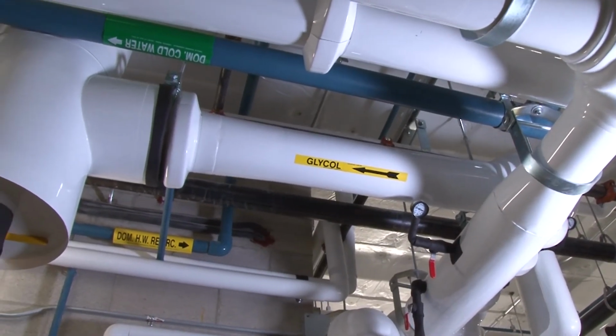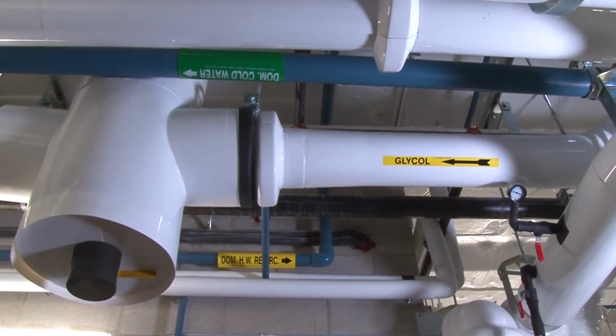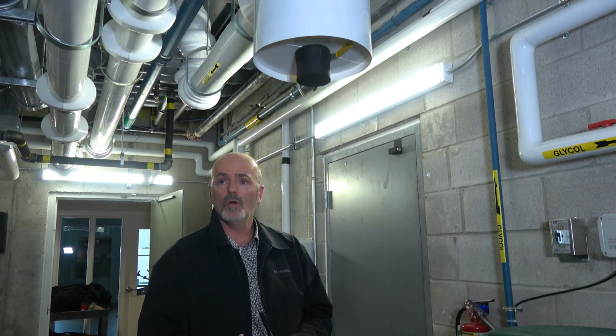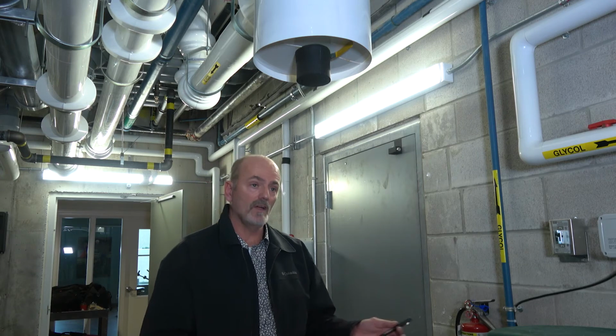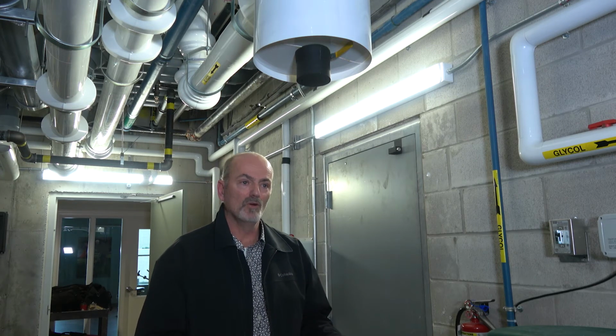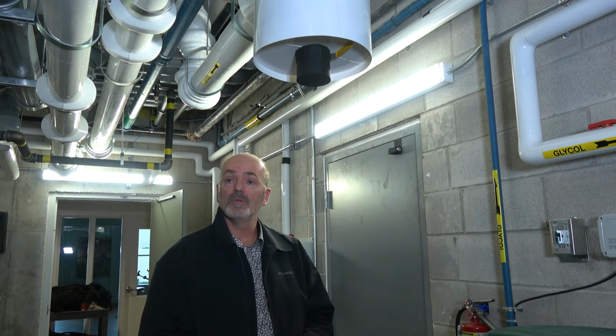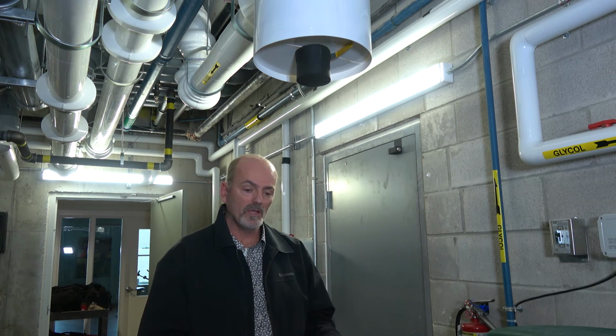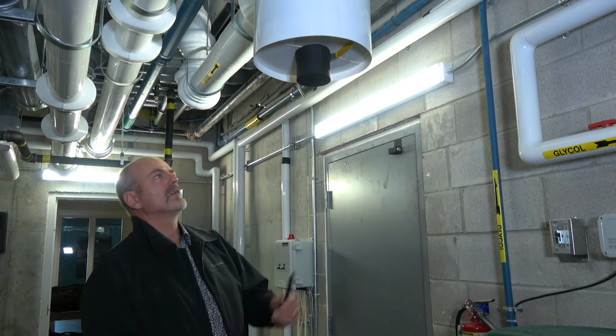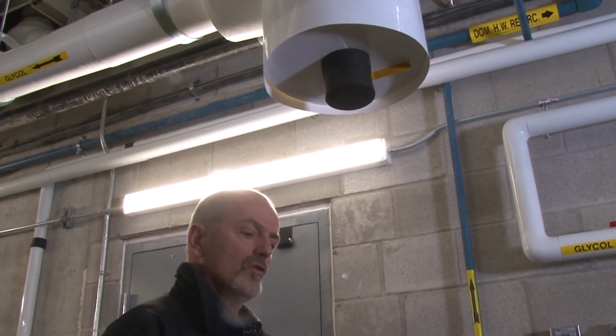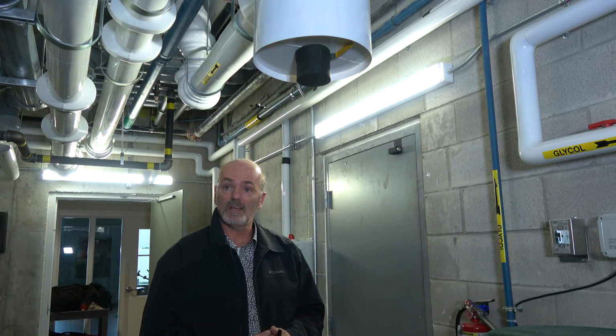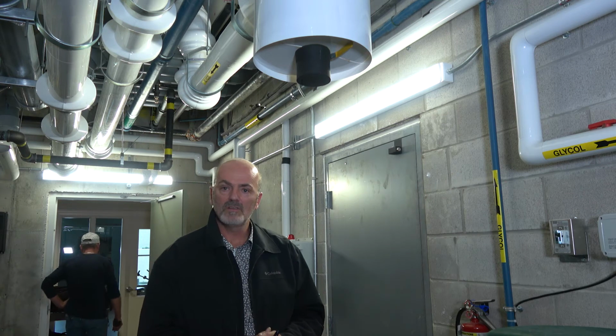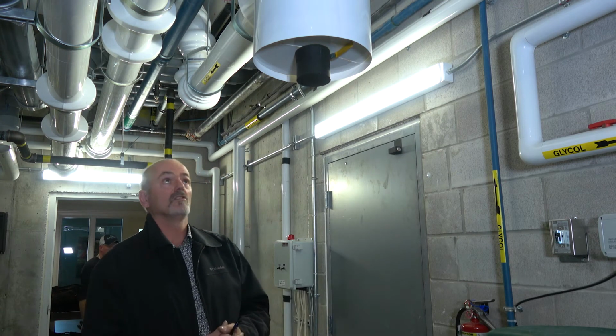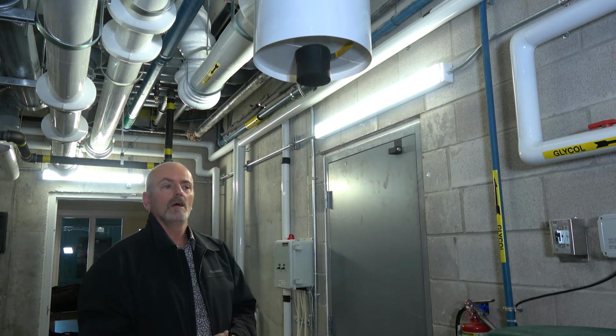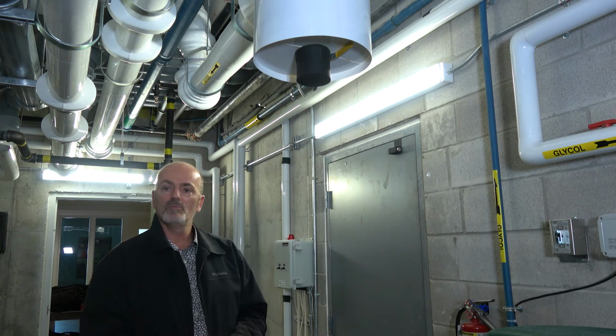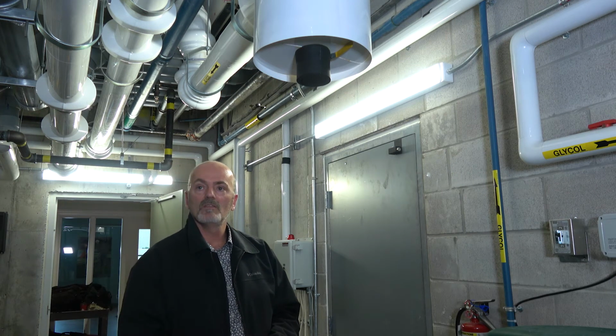All right? There is potential for that valve and float mechanism to get plugged and malfunction, either shut or open. Shut means you get no air removal, so you're going to have air in the system, which isn't healthy for the system, or you're going to have removal all the time, which means you'll have a visible leak off the top of the air valve, and it will need to be inspected, replaced, repaired, or cleaned. Okay? On the bottom there is a drain that can be used to remove any debris that accumulates in the tank as well. Other than that, there's no real maintenance of the tank. It's just an ASME pressure vessel, and it's designed to allow the flow to slow down in a bigger chamber, and the Pall ring bed to accumulate the air and allow it to break away and rise up. It's one of the most effective air eliminating devices on the market today.